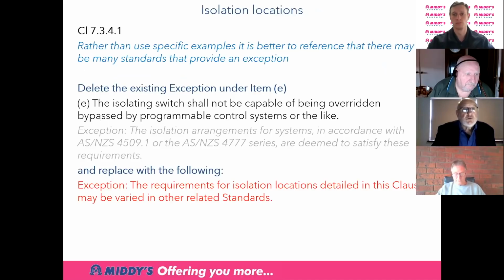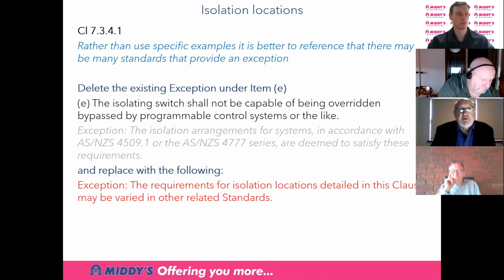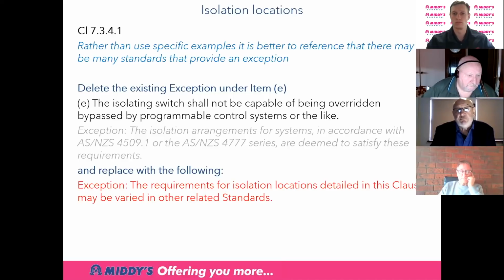What we've done in this clause 7.3, there were specific examples that were used to reference the fact that you need an isolating switch that shall not be capable of being overridden by a programmable control system or the like. And what we've done in the exception is we referred to that standard 4509 part 1 is standalone PV systems, and 4777 is inverters for PV systems. So what we've done is we've just replaced it, that those requirements about being overridden by control systems for isolating switches can be varied by other related standards. So we've just taken the specifics so that people don't see it as just aimed at PV. It's aimed at a whole lot of other standards as well. So we've just tidied that exception up.